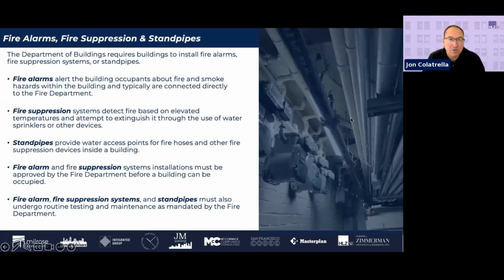So starting with a fire alarm system, this is a system that we all know about that alerts building occupants to a fire and smoke hazard in the building. They're typically all connected to the FDNY directly, so that when a fire alarm goes off, the FDNY is immediately being dispatched to come to the building as people are starting to egress the building. A fire alarm system can be triggered by a smoke condition, a heat condition, or a water flow condition. A lot of people don't know about the water flow condition, so that if a sprinkler head is discharged, water flow is now in the system and the fire alarm is set off, dispatching the FDNY. Additionally, there are tamper switches on valves. If a valve is inadvertently closed to cut off water flow, that will also set off the fire alarm system, dispatching the FDNY.